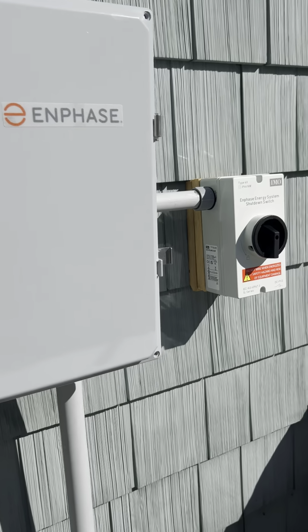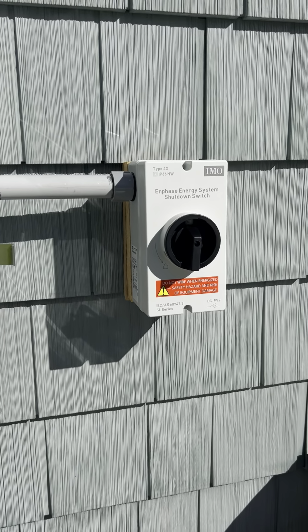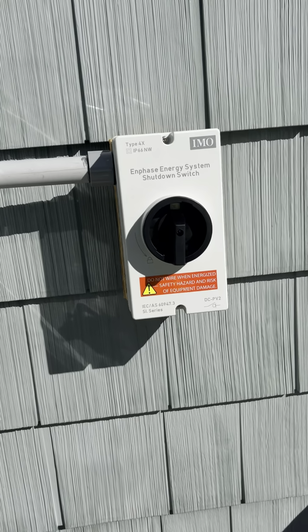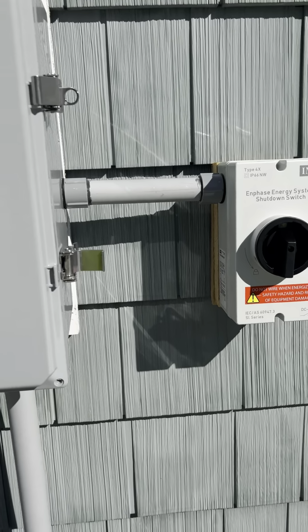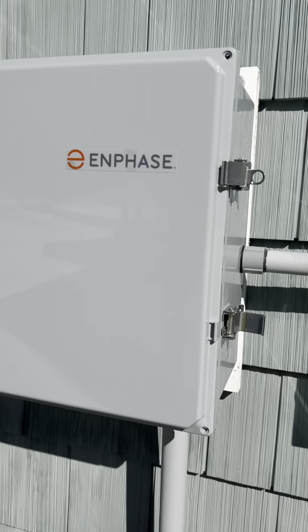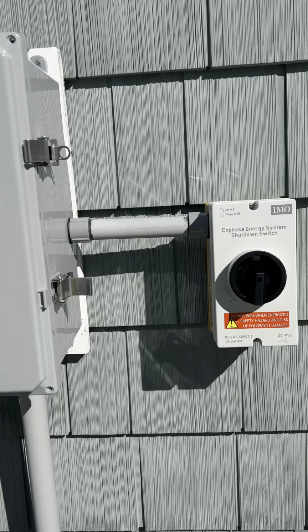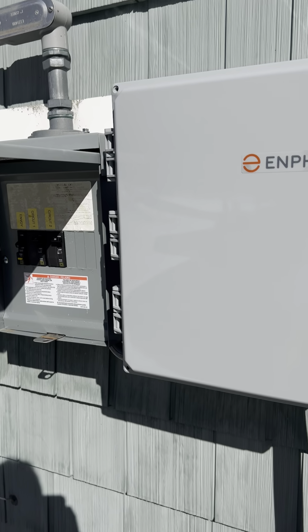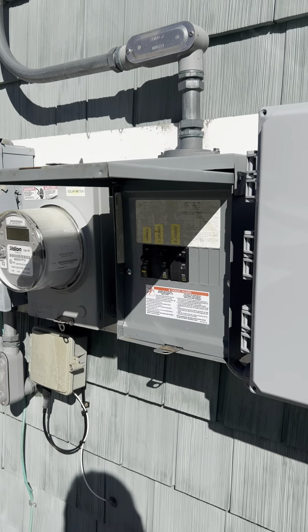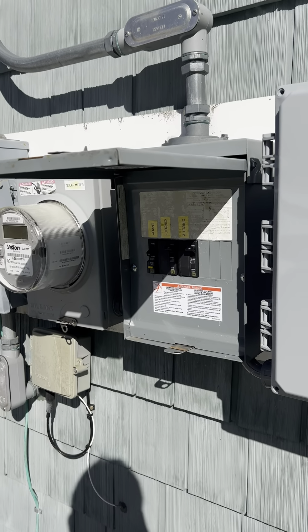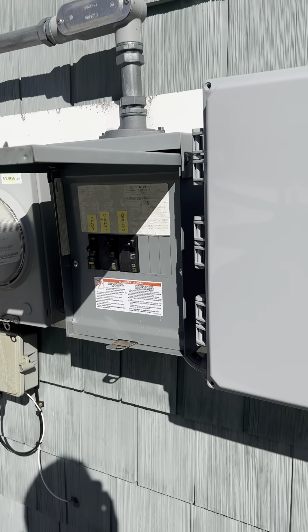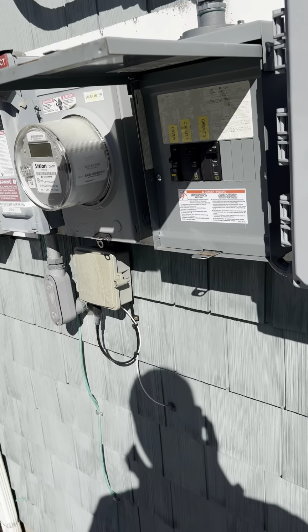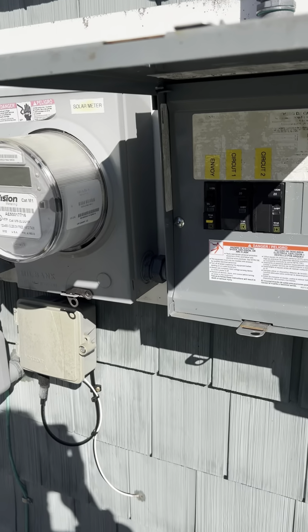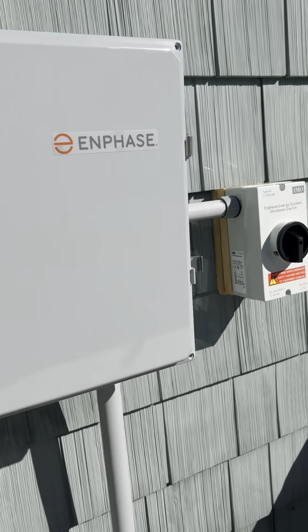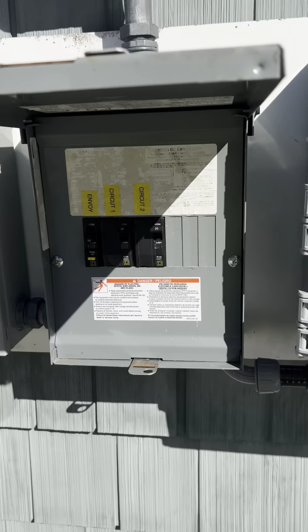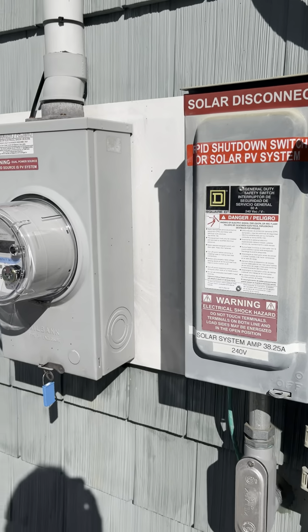Now, in this specific situation, there's really no need for the Enphase rapid shutdown switch, and that's really for one reason. This system doesn't have microgrid capability in terms of forming its own microgrid. The IQ8 series can form its own microgrid. So in this situation where the batteries are fully depleted of power, the PV can form its own microgrid without the use of the system controller communicating and discharging from the batteries. So this M215 system cannot support that. So there's no need for the rapid shutdown, but we installed it anyways in case the homeowner needs or wants to upgrade in the future.